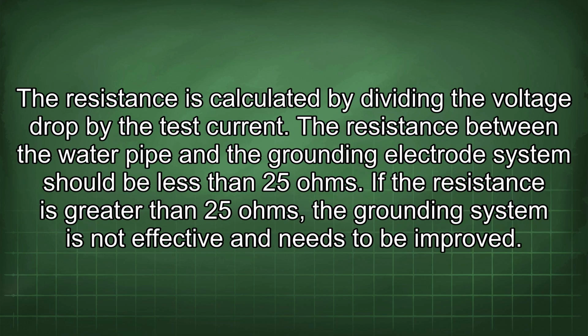The resistance is calculated by dividing the voltage drop by the test current. The resistance between the water pipe and the grounding electrode system should be less than 25 ohms. If the resistance is greater than 25 ohms, the grounding system is not effective and needs to be improved.